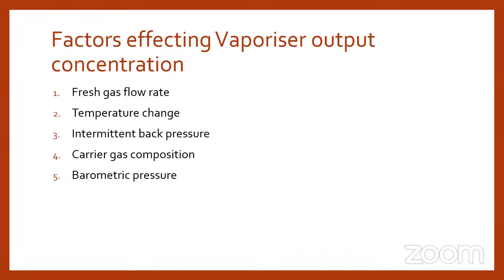The second thing is temperature change. When the chamber is heated, or the temperature is high, then the reactivity of the liquid present in the vaporizing chamber will be high. So the amount of vapor production will be high, and the concentration of the vapor coming out of the vaporizer will be more. So the temperature is directly proportional to the vaporizer output concentration. If the temperature is high, the output will be high, and if the temperature is low, then the output will also be low. Intermittent back pressure, I'll explain in detail in later slides.